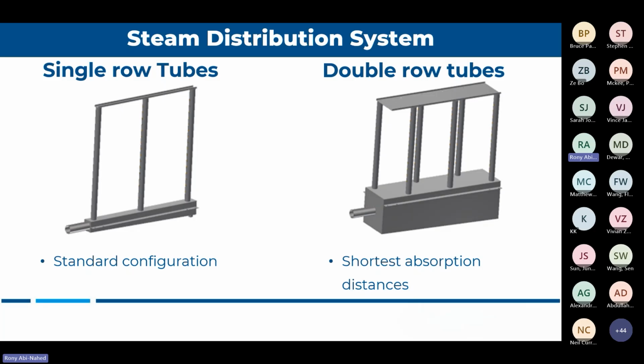So we design the job, we go into the absorption distance he's asking for, and then once on site, it starts condensing, while we're supposed to be good. So you go on site and you see that the design condition really changed. Like the outside air, it's not 40 now, it's 60, or the air hitting the grid, it's not 55, it's 52. That would change your absorption distance completely.